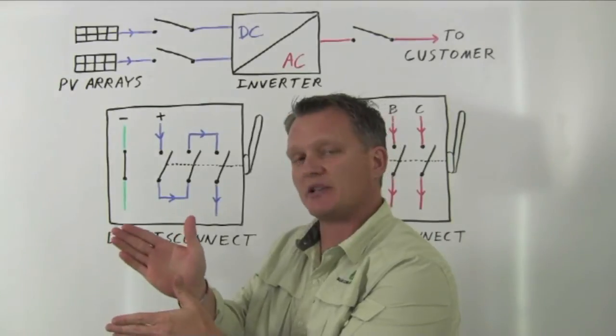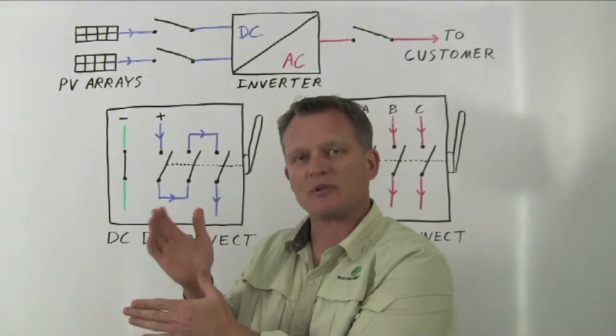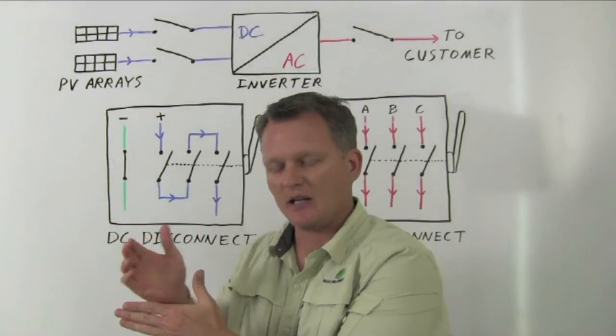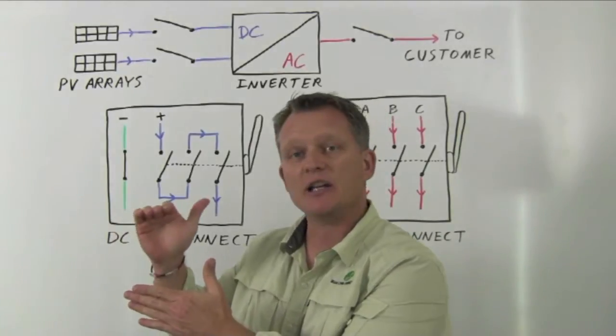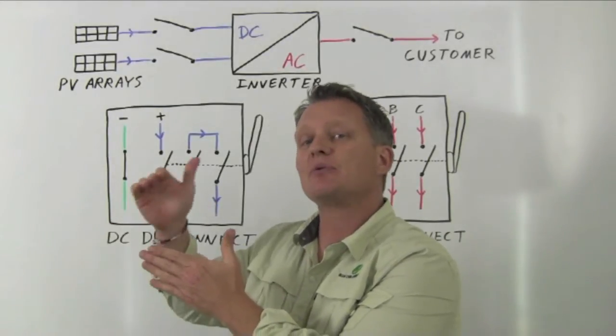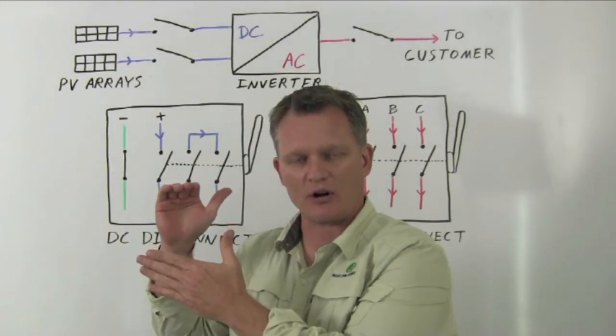You think the current stops immediately, and that's not the case. What actually happens is that current continues to flow even through the air gap in the form of an arc. Now, that arc puts out an enormous amount of heat.